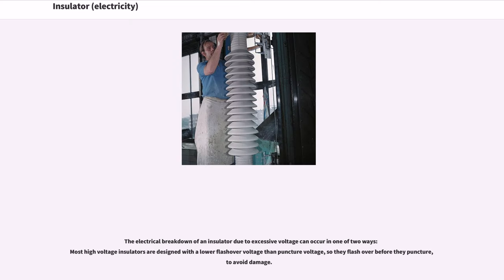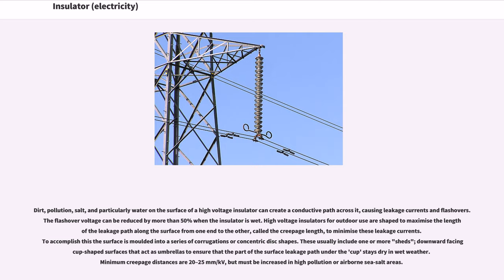The electrical breakdown of an insulator due to excessive voltage can occur in one of two ways. Most high-voltage insulators are designed with a lower flashover voltage than puncture voltage, so they flash over before they puncture, to avoid damage. Dirt, pollution, salt, and particularly water on the surface of a high-voltage insulator can create a conductive path across it, causing leakage currents and flashovers. The flashover voltage can be reduced by more than 50% when the insulator is wet.